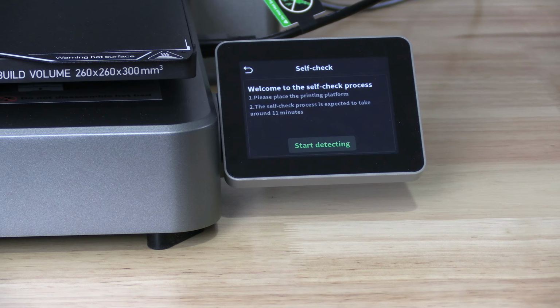Keep in mind, there is most certainly going to be a firmware update required, and you will need to run calibration after that firmware update. So, my apologies, we are going to run calibration twice. The good news is, this first calibration will at least let you know the machine is working.